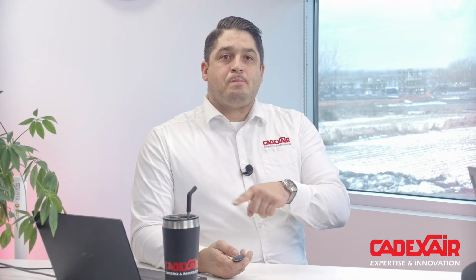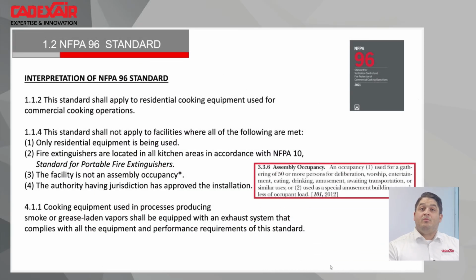So, to return to the presentation, the facility is not an assembly occupancy. Technically, as soon as you have used by 50 or more persons for gathering, deliberation, worship, entertainment, eating, drinking, amusement, awaiting transportation, or similar use, you are an assembly occupancy and you will still need to comply with NFPA 96. And if people are waiting for the bus near a residential electric stove, you will need to comply with NFPA 96. So that's a big limit.